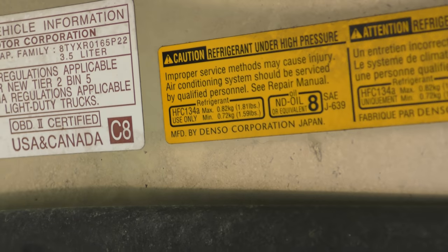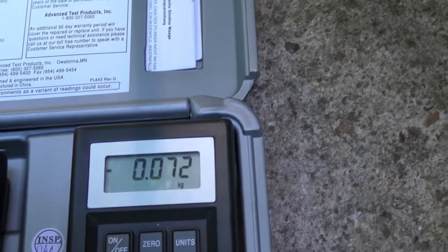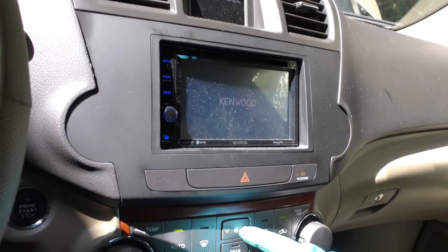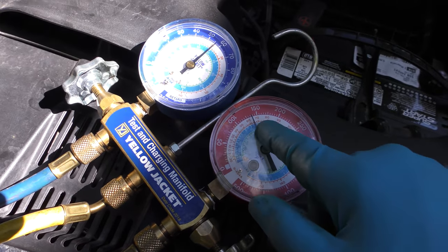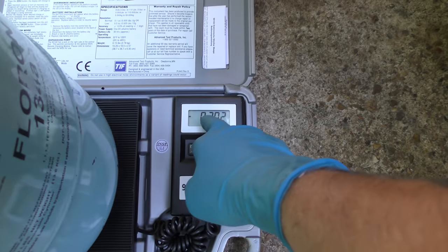As we can see here, the maximum is 0.82 kilograms. We've got the scale at zero, we'll open it up and add 0.82 kilograms — when this hits 0.82 it's done. We'll go inside and start it up with the compressor running; it'll fill up better. Put the AC on full blast, outside air, then we'll watch the pressure. This is already starting to come up, which it should. The high side will always be higher while you're filling it up. That's probably some idiot who got air in it or overfilled the system.